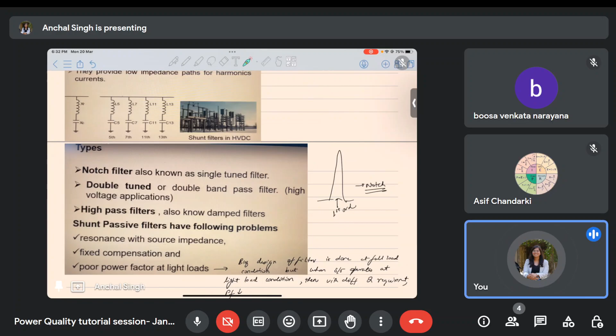Then double tuned band pass filter means it will allow two frequencies to pass. Let me say that I want first order and third harmonic, so I will tune my filter for first and third harmonic. Then there are high pass filters, also known as damped filters. A high pass filter will allow all the frequencies beyond certain levels. Suppose I want all the harmonics greater than the fifth harmonic to pass. So I will tune my high pass filter to be around the fifth harmonic, so all the frequency components higher than the fifth harmonic will be passed.